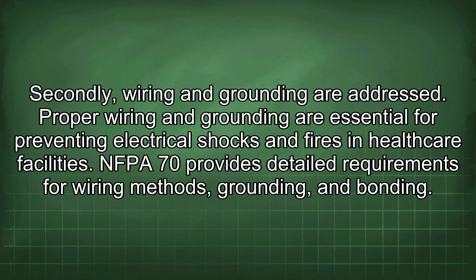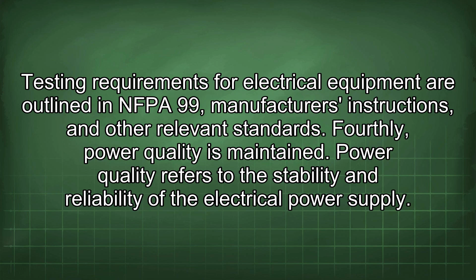Thirdly, equipment testing is covered. Electrical equipment used in healthcare facilities must be regularly tested to ensure that it is operating properly and safely. This includes equipment such as patient care equipment, diagnostic equipment, and life support equipment. Testing requirements for electrical equipment are outlined in NFPA 99, manufacturer's instructions, and other relevant standards. Fourthly, power quality is maintained. Power quality refers to the stability and reliability of the electrical power supply. Poor power quality can damage sensitive medical equipment and disrupt patient care. IEEE 3003 provides guidance on power quality management in healthcare facilities.